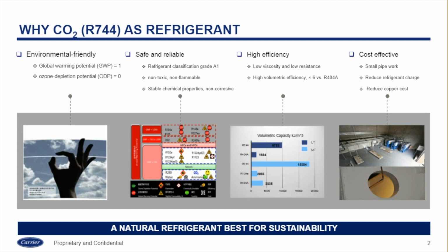Coming to the third and the fourth one, CO2 has very high efficiency and is cost-effective compared to other refrigerants like ammonia or HFCs such as R404A or R410A, with good heat transfer performance especially at low ambient temperature and in low temperature applications. So that is the most effective use of CO2 as a natural refrigerant. Okay, next page, please.